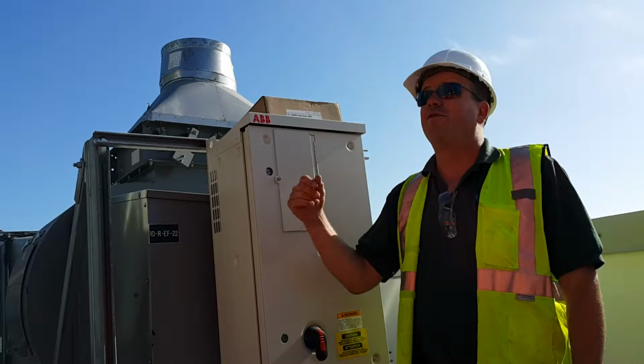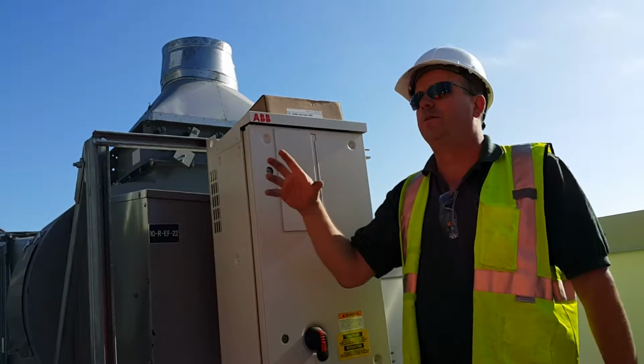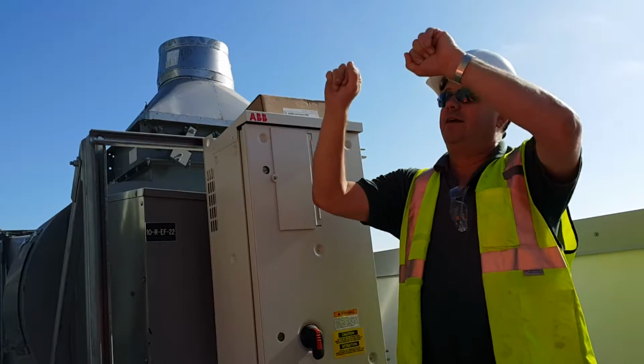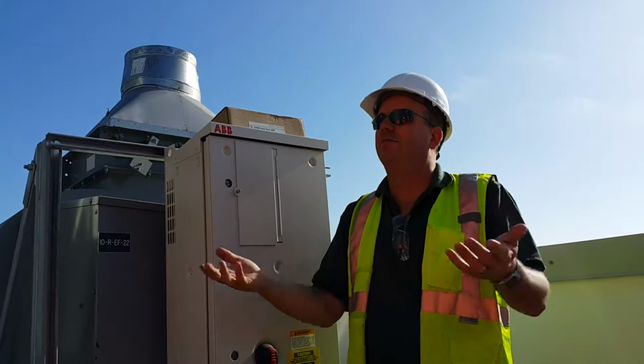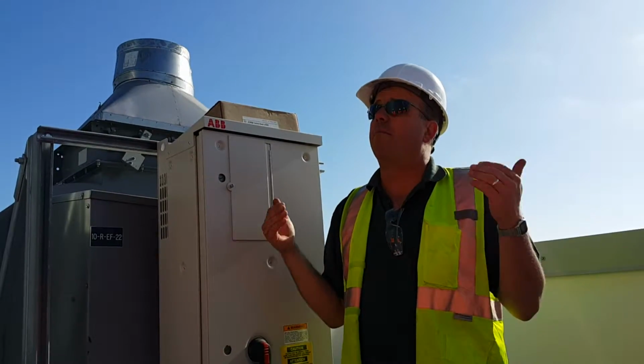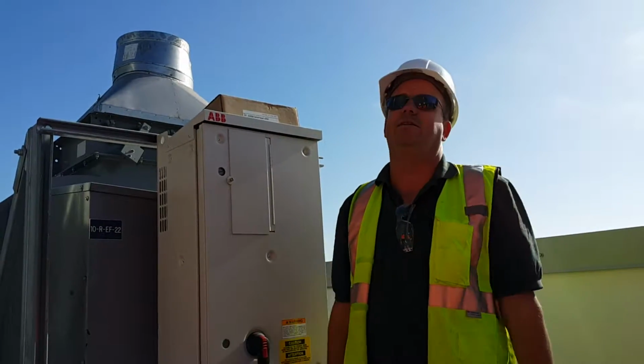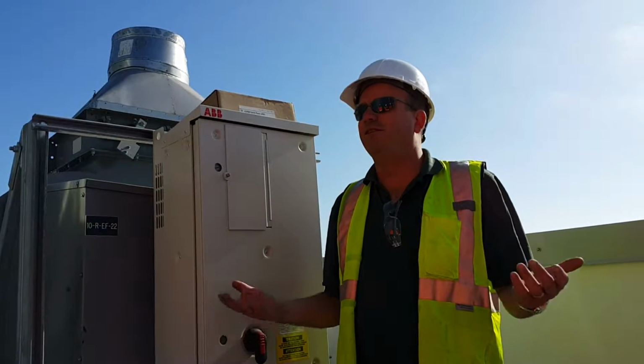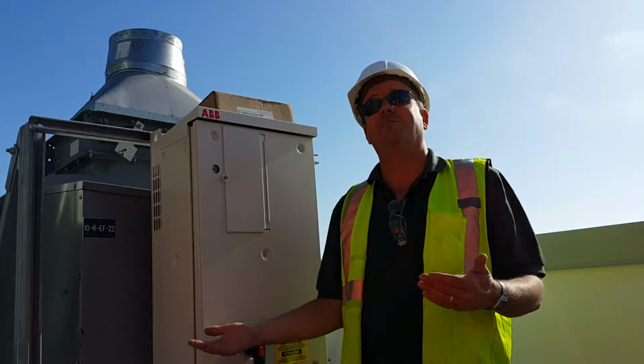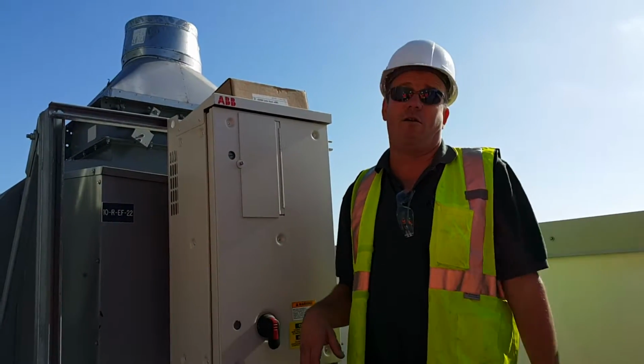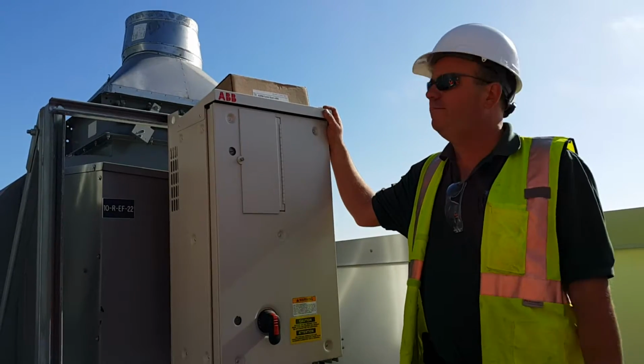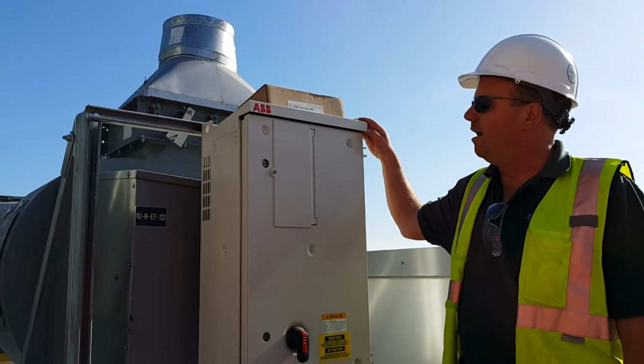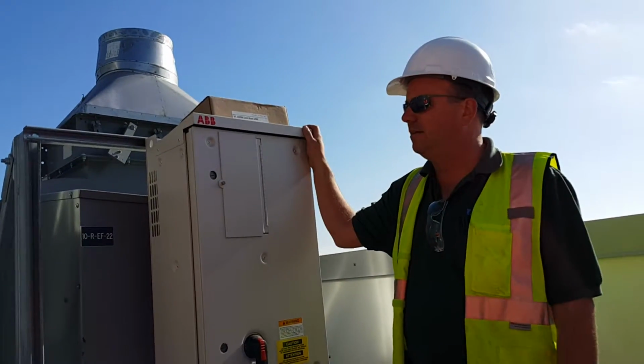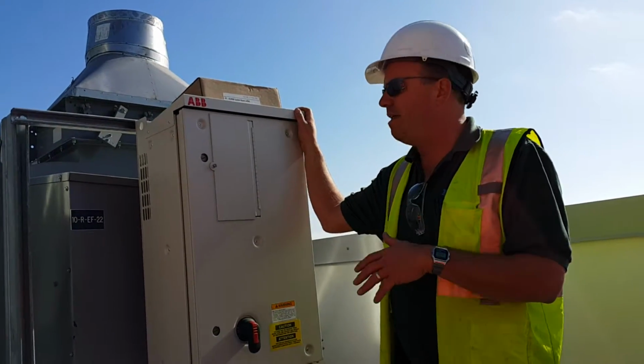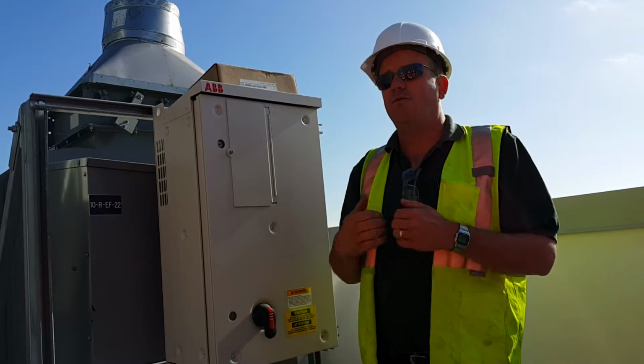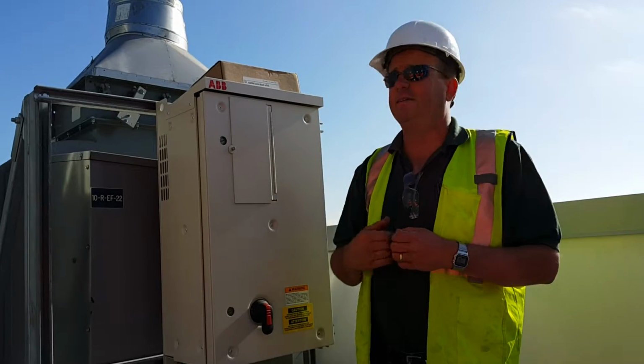You know, there's also, if you have fire shutdown and it opens up the contacts, it'll say alarm 2021. It flashes at you. Well, it says start enable 1 missing. That's the enable circuit saying, my enable is gone. My ability to run is gone because I'm being told to shut down. Is that really an alarm? No, it's just a notification. Hey, just want to let you know the reason I'm not running is because I have a safety open. I'm not supposed to run at all. So don't freak when you see alarms. That happens quite a bit. Well, fault. Okay, that's a condition. And again, can't reiterate enough that if you see a fault, doesn't mean the problem is in the drive. The drive may have shut itself down to protect the motor, protect itself, and so on.